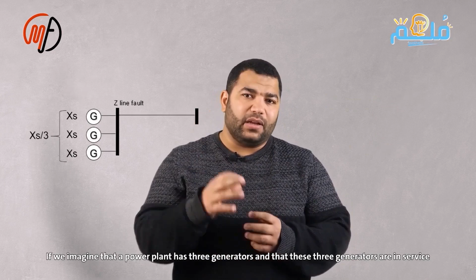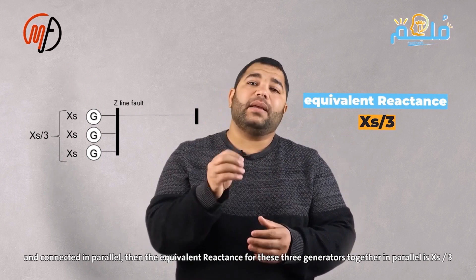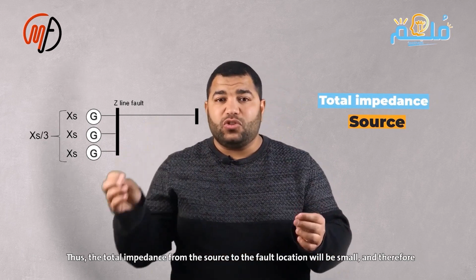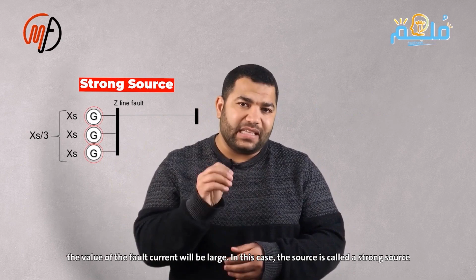If we imagine that the feeding station has 3 generators and all 3 generators are operational and connected in parallel, then the equivalent source impedance for the 3 generators together is XS divided by 3. Therefore, the total impedance from the source to the fault location will be small, and as a result, the fault current value will be large. In this case, the source is called a strong source.